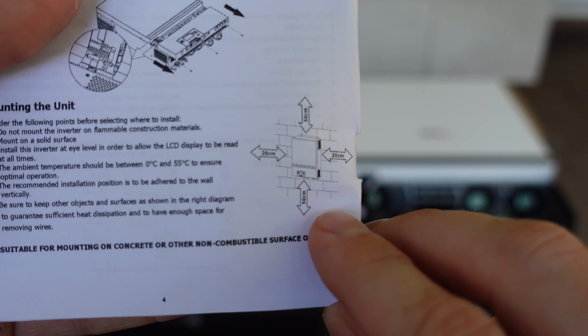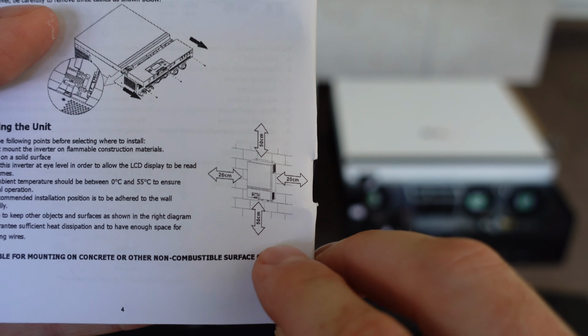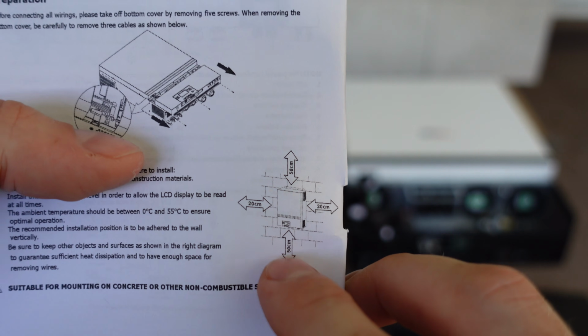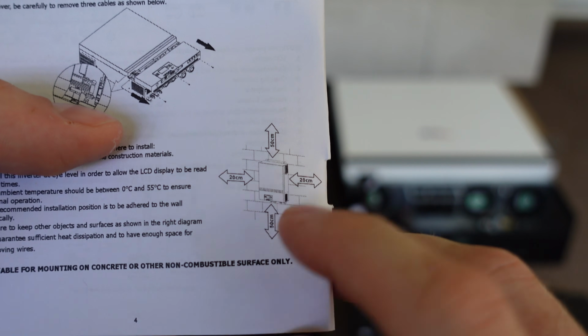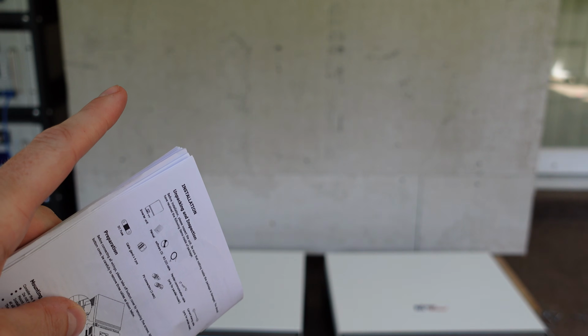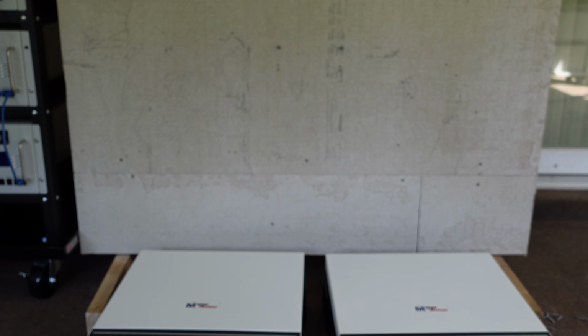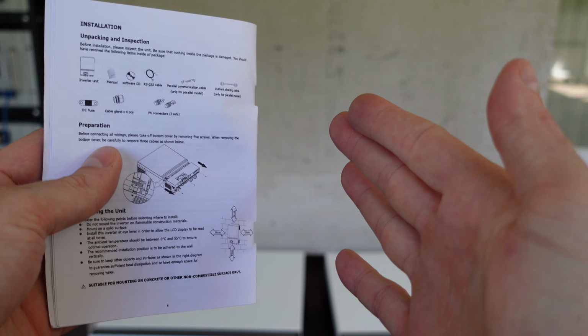Additionally, they have some spacing requirements here. They want 50 centimeters above and below the inverter and 20 centimeters to the left and right of the inverter. Now I do have limited space here, and this is a temporary test setup, so we're going to squeeze them a little bit tighter here.